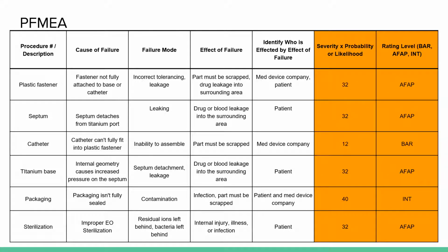For the PFMEA, we looked at different failures that could occur as a result of issues in the manufacturing of the device. This list is not extensive, but highlights some key points. So an example would be if in the packaging, a failure could be if the package wasn't fully sealed, which would result in contamination. The effect with that could cause infection if implanted in the body, so the part has to be scrapped, and the patient and the device company are affected by this.